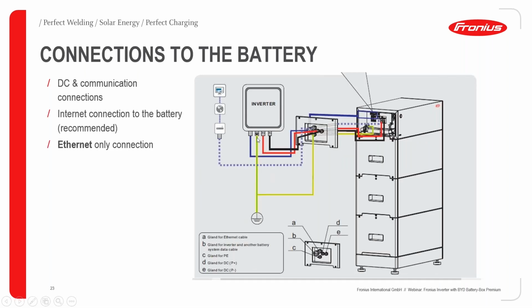So these come from the inverter - your earth, your DC coming in, and your communications. We recommend you don't necessarily need communication to the battery - it does have a web server in there, and as far as I know, for the warranty you don't have to have it connected. However, we do recommend having it because it gives BYD a lot of insight as to what's happening.